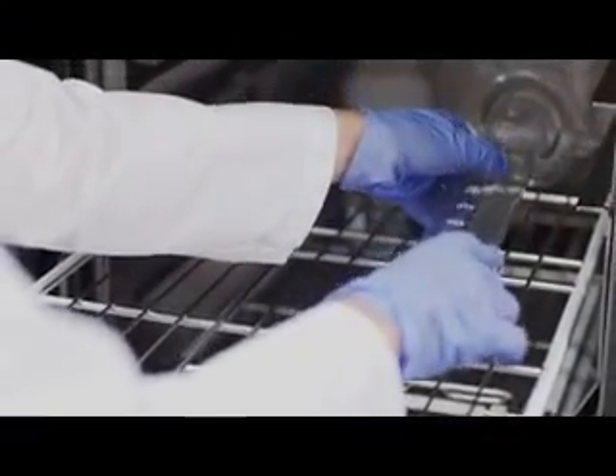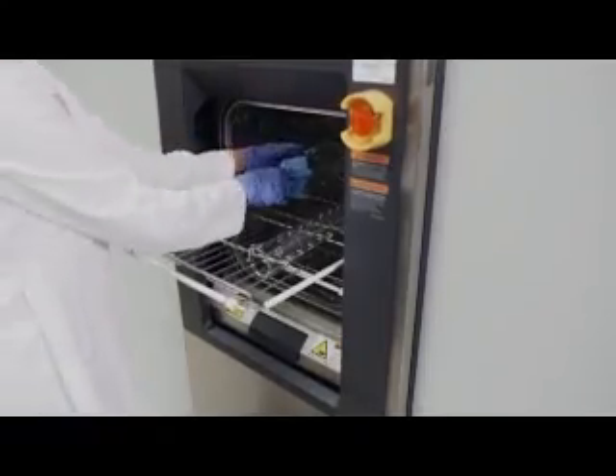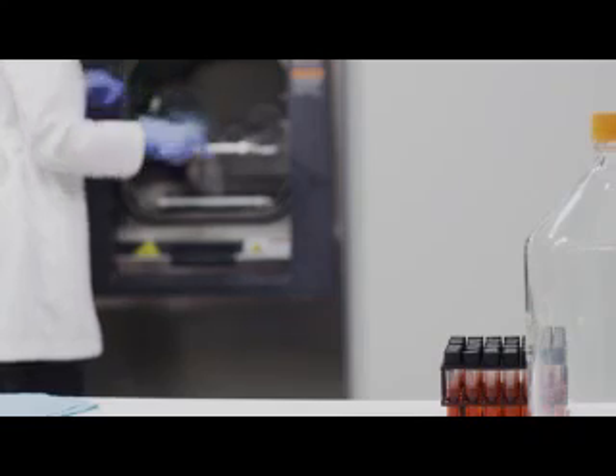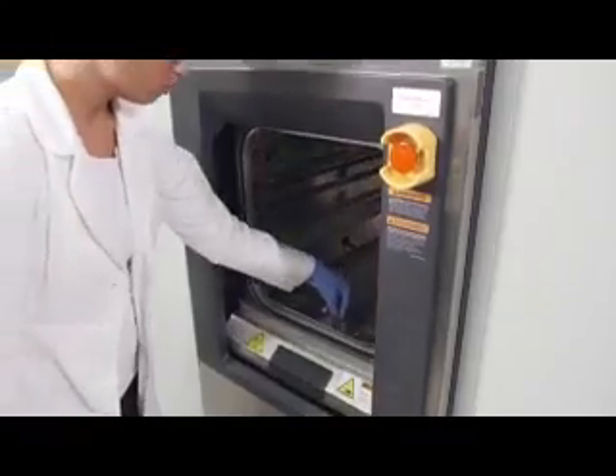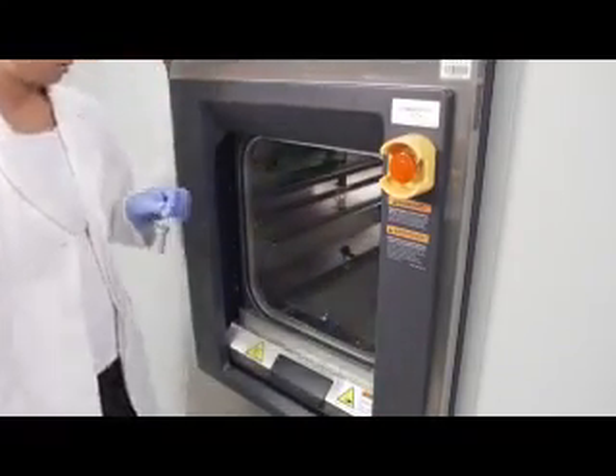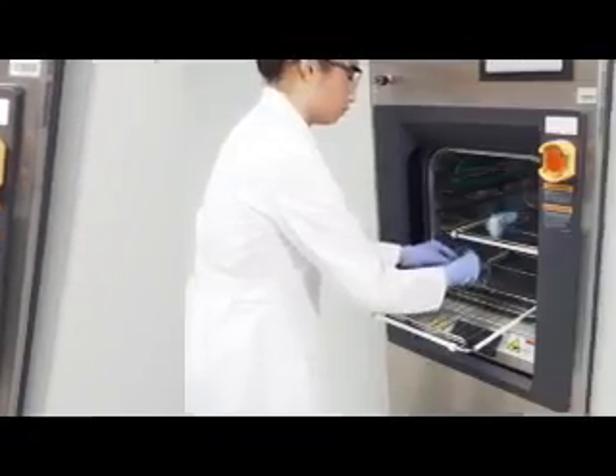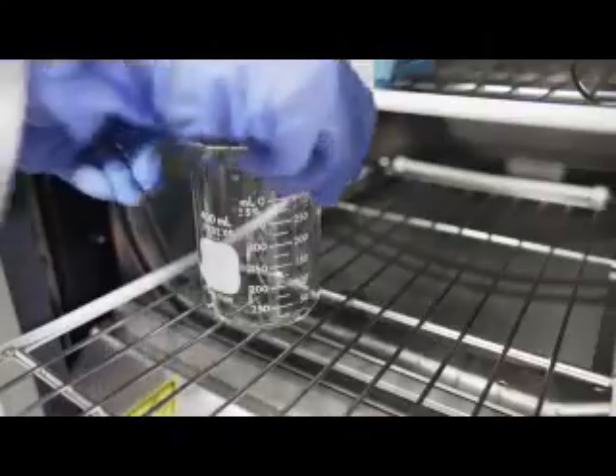When preparing your load, there are two important factors to remember. Steam must contact the load, and air will prohibit this from happening. For this reason, during the conditioning phase, the air is removed from the sterilizer. This is accomplished through either gravity air displacement, as the steam pushes the heavier air down the drain, or it is accomplished through the use of a vacuum, which pulls the air out of the chamber. It is important to load your items with this in mind.